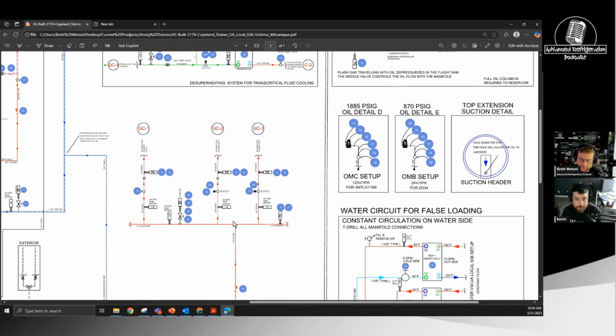So let's talk about this for a sec, because we had theories on how we would do pump out or whatever. So they are not doing pump out -- they're leaving the gas in the coil, and there's check valves on the drop legs. According to them, the amount of gas left in the coil isn't a problem if you split properly, they're not having an issue. I think it may need split or a pump out, but on this rack it's definitely not going to need it -- it's too small and it's getting blown down anyway when they're done.